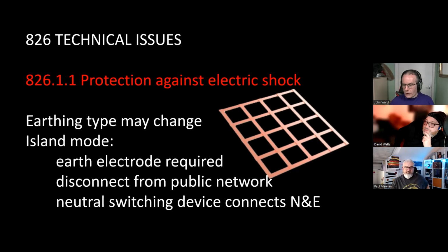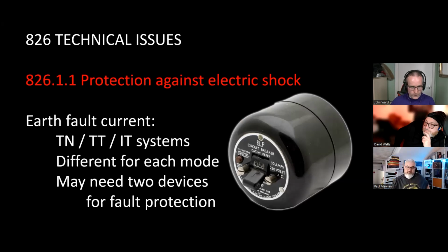Protection against electric shock. The earthing type may change. So if you're connected to the grid, it might be a TN system. If you're going to island mode, it might be a TT system. So just by disconnecting from the grid, you may be changing the type of earth you've got for your installation. In island mode, you do need an earth electrode disconnected from the public network completely, and you'll also need a neutral switching device to either connect or disconnect the neutral and earth connections.